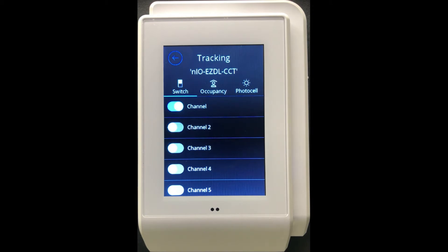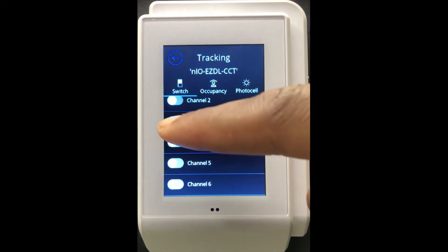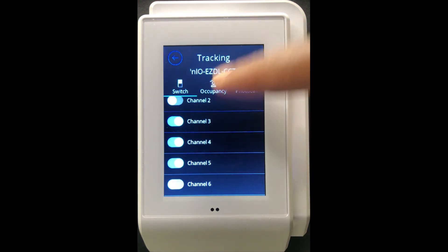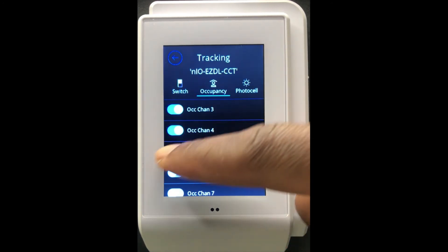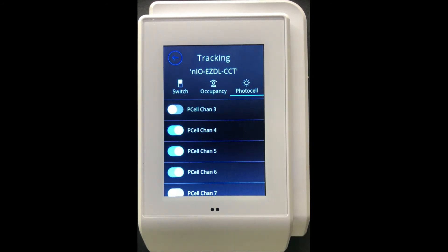One key thing to note is that a pole or an output device can actually track multiple channels simultaneously. Unlike an input device, which can only broadcast to one specific channel, an output device can track multiple channels simultaneously. For example, this particular pole can track channel 3, channel 4, and channel 5 as switch channels. I can also go under occupancy channels and configure it to track occupancy channels 3, 4, and 5, and do the same for photocell channels as well.